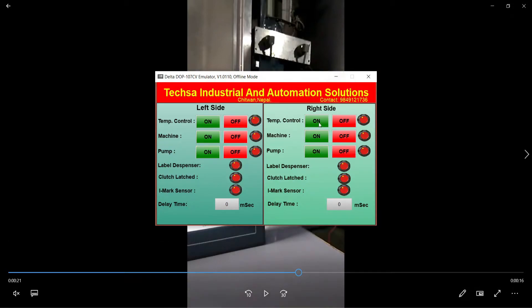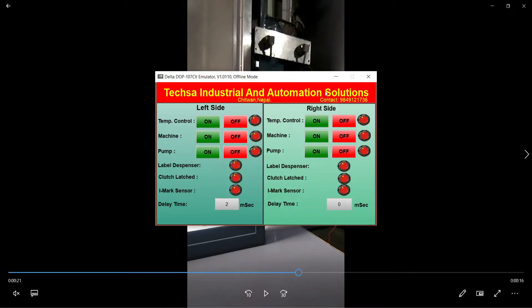That delay time is for when the I-Mark sensor senses the mark on the wrapper. Suppose the delay time is two seconds - the wrapper will stop after two seconds, then it gets the sealing. The time is zero seconds here because zero seconds works fine. If you need longer parts, you can increase the time. This part is for half liter.